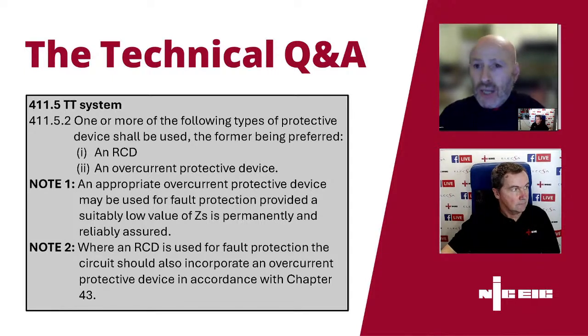There's a bit more information for those who want a little more on it. There's also an informative note included within that regulation, which states that an appropriate overcurrent protective device may be used for fault protection, provided a suitably low ZS is permanently and reliably assured. So you've got to guarantee you're going to maintain that low ZS value.